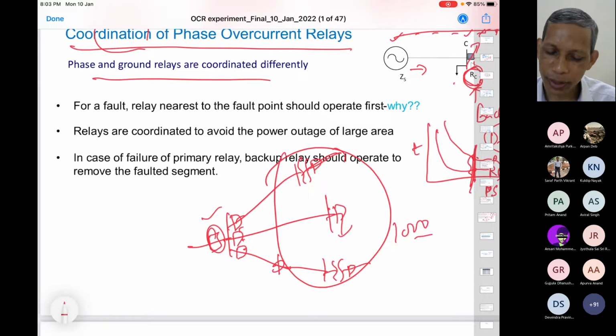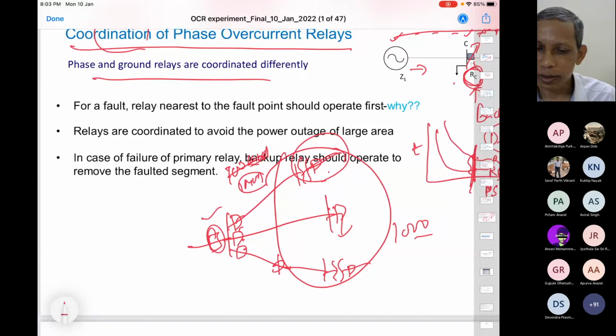So therefore, what is your provision? You provide that this will be having hundreds of customers. I can put it like this. For these 100 customers, I can put a transformer of, let's say, 100 kVA or 1 MVA, and I can put a breaker and relay element. Agree? In CESC Kolkata, they don't have a breaker for the LT system. They have only HRC fuse. So my point is that your question is what to put a breaker on and all these things.